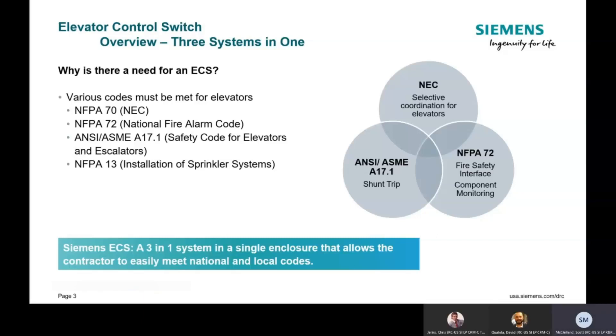The national codes prescribe the requirements for sprinklers, elevators, and electrical equipment. These are NFPA 70, NFPA 72, ANSI ASME A17.1, and NFPA 13. The elevator control switch has a system that includes a shunt trip, fuses, and a communication method with the fire alarm control panel. So it's really three systems in one.